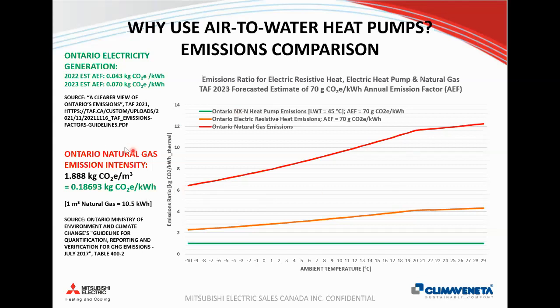But if we compare the electricity emissions with the natural gas emissions and we normalize it to the heat pump COP curve that we saw earlier, we can compare how many times more emissions are associated with an electric boiler or natural gas producing the same amount of heat. So our electric boiler is about 2 to 4 times more emissions and 2 to 4 times more to operate. This is essentially our COP curve because our heat pump has a COP curve and our electric boiler always has a COP of 1. So again, this is normalized to the emissions of the heat pump.